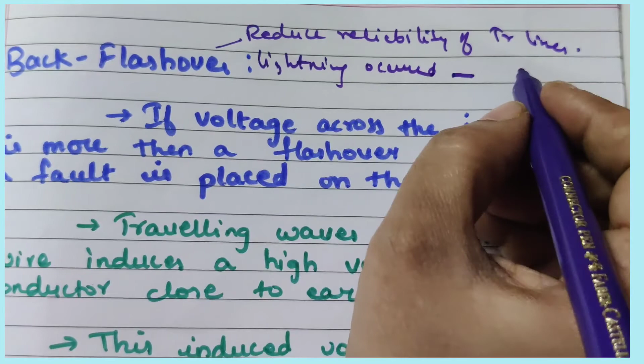The current produced in that earth wire is what causes one phase to flash over, and that phenomenon of producing these wave currents is called back flashover.